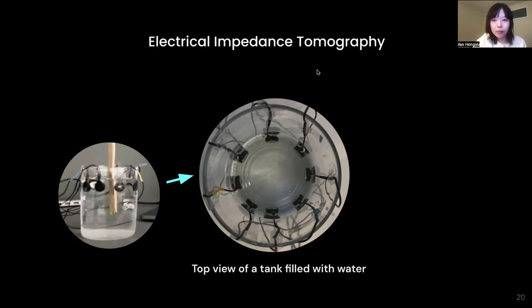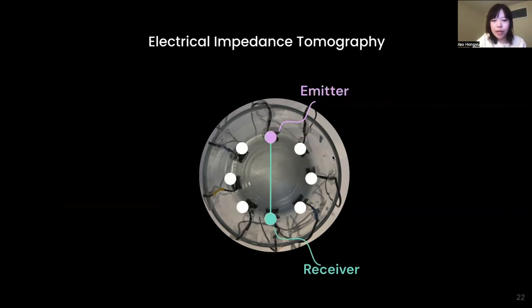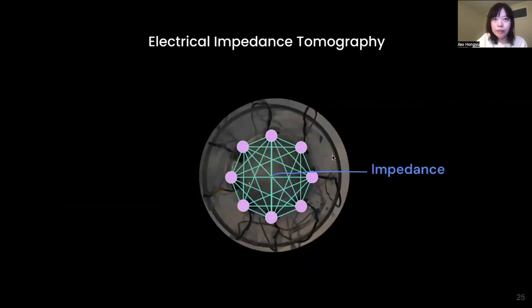Here is the top view of a tank filled with water. Imagine this is the object that we want to image. Electrical impedance tomography involves attaching several pairs of electrodes onto the objects. For each pair, one electrode works as an emitter and one will be the receiver. From analyzing the signals, we will be able to calculate the resulting impedance caused by the passage of the current. We can multiply the receivers as well as the emitters, and from the combination of the impedance values, we will be able to get the 2D reconstructed image of that object.